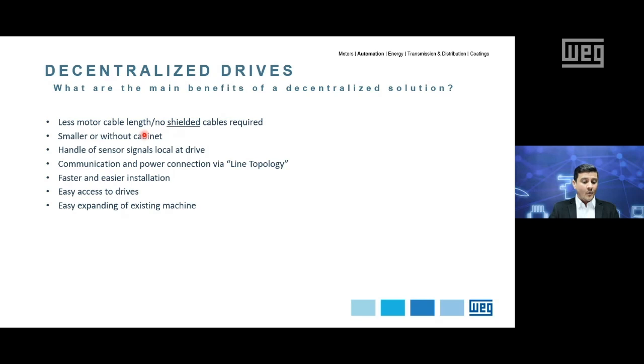Further to this, we are aware that when there are long cable distances between the VSD and the motor, an output filter, for example, a load reactor or a dV/dt filter, could be required in order to reduce the voltage peaks which are delivered to the motor terminals. If I can take this component out of the solution, we can further reduce the total cost of the system, and as a consequence, the control cabinet can be made smaller, or for some applications, it's also possible to remove it altogether, which again turns into potential savings. It's important also to mention the lower EMC interference, considering the VSD is now mounted close to the motor, having a short output cable length. So this is a very important note as well.